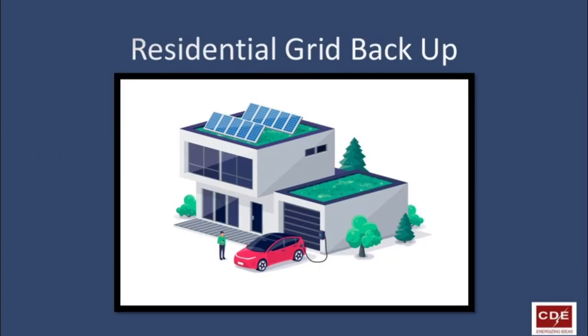One of the most difficult tasks in an off-grid residential system that relies on solar power and battery backup is how to deal with high starting current demand loads, such as air conditioning and refrigeration compressors. These types of starts can put so much demand onto the house's power grid that you actually see a voltage drop. One solution is to place a supercapacitor bank co-located with this high-demand load to provide those first few milliseconds of current flow. Using supercapacitors to handle short, high-peak demand currents can allow you to use a smaller main battery bank.